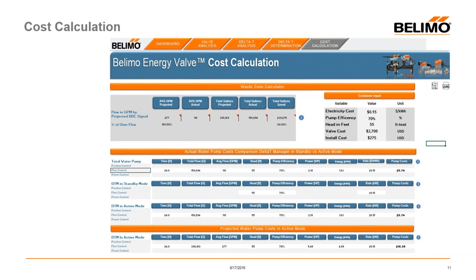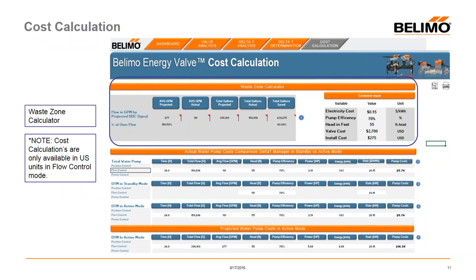The next and last calculation tab is the Cost Calculation tab. We start with the dashboard for quick navigation. The waste zone calculator looks at the projected flow rate through the valve when the delta T manager was active — it calculates what the flow would have been through the valve at the DDC set point. In this example, the projected flow rate if the DDC was in charge would have been 277 GPM, but because the delta T manager was invoked we only actually flowed 110 GPM — resulting in a 60% savings in pumping.